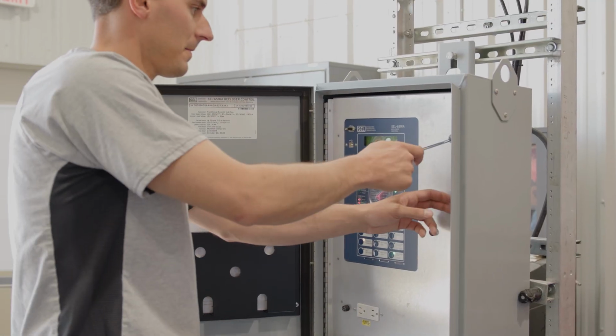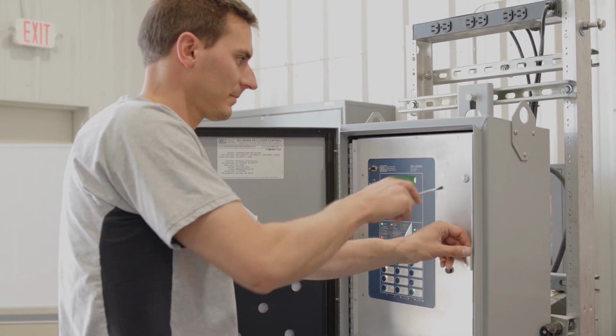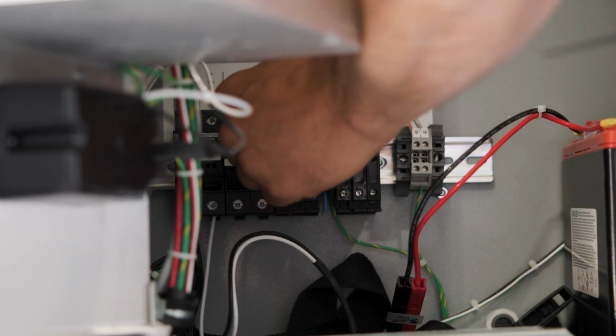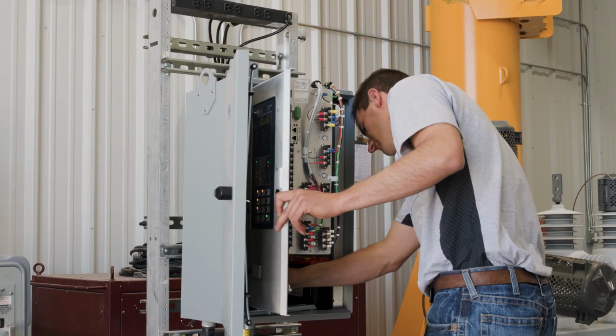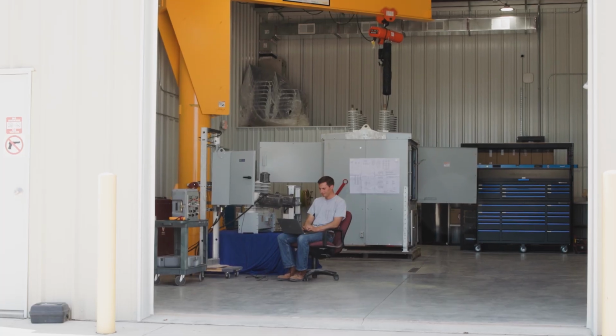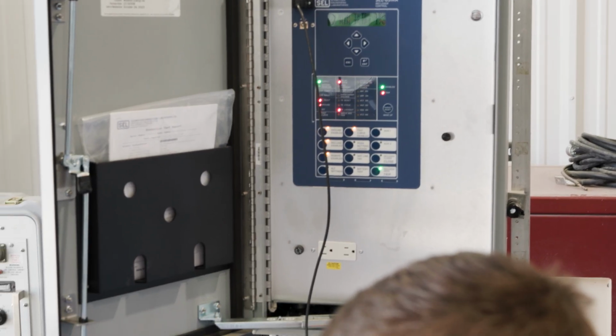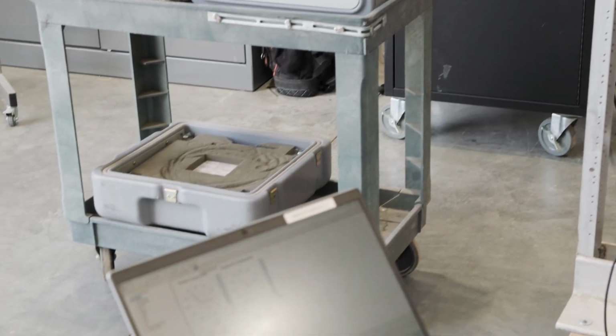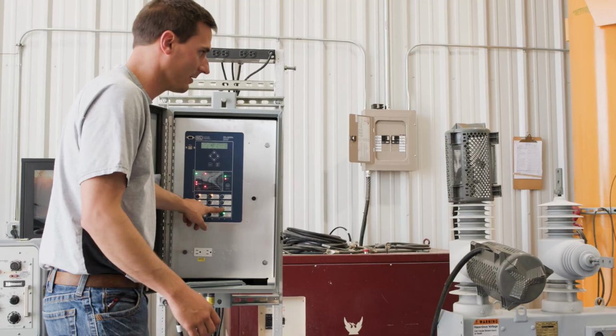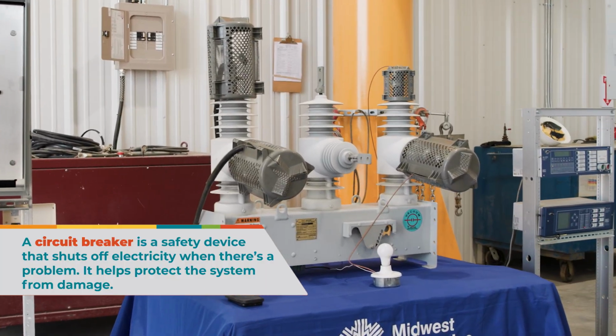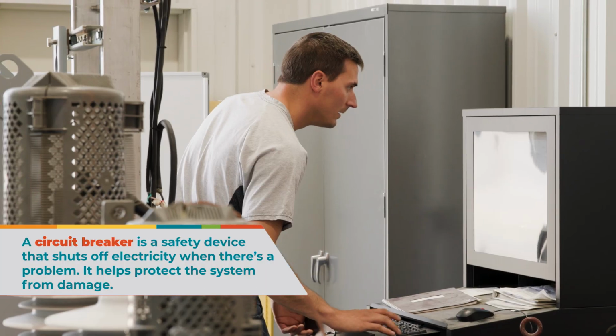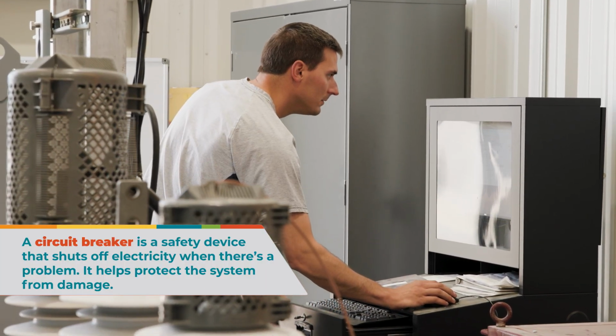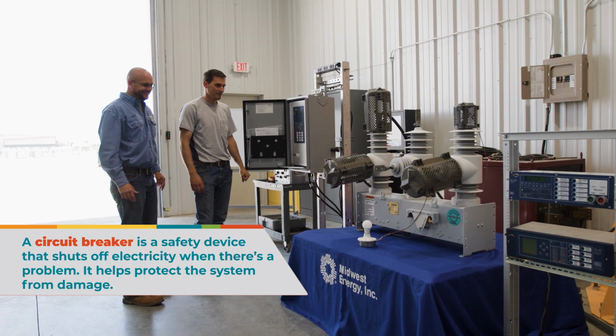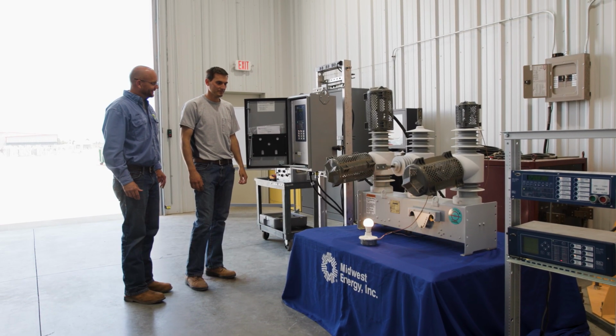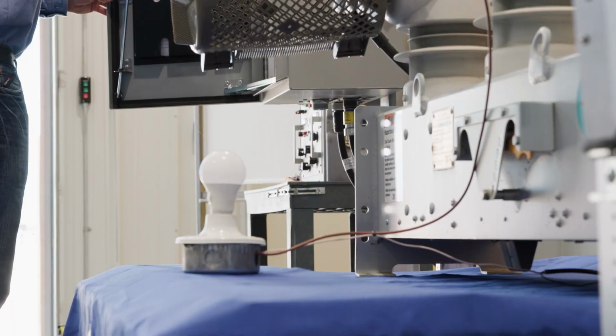So my job revolves around the programming, installation, repair, and maintenance of these devices. Some of this work is done in a warehouse like this one to program and test the relays. Before installing, we need to know the relays are functioning properly. That means we make sure they shut off the correct breakers and they do it at the proper speed, which is what your relay team and my relays have in common. Relays need to detect faults super quickly to protect problems from magnifying and shutting down large sections of the grid.